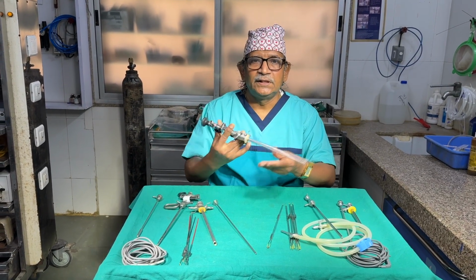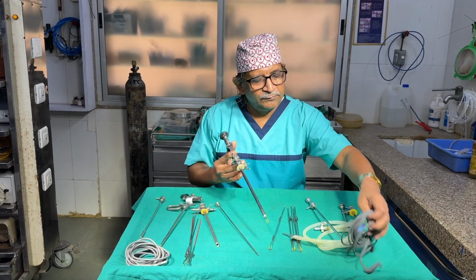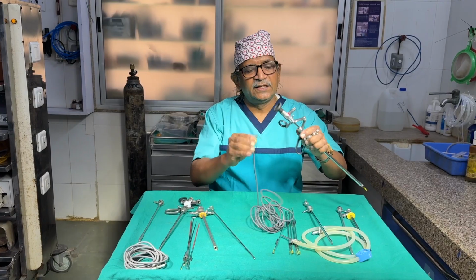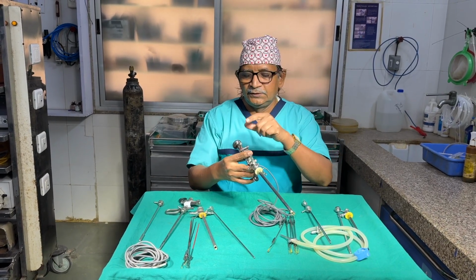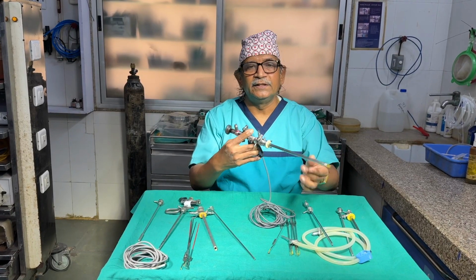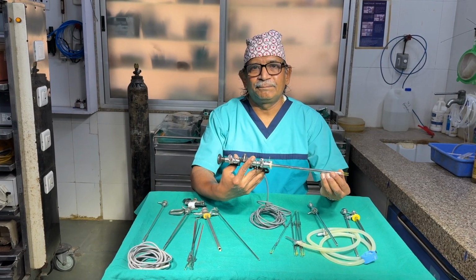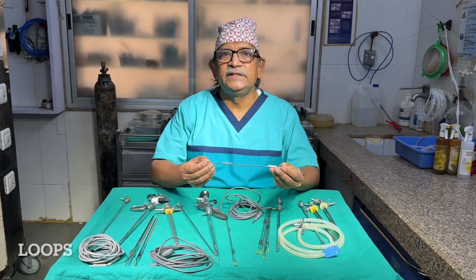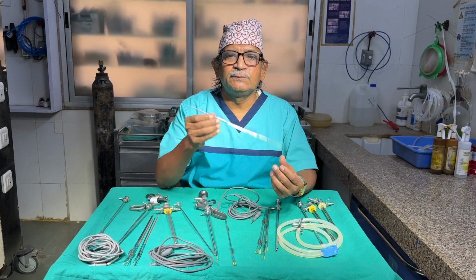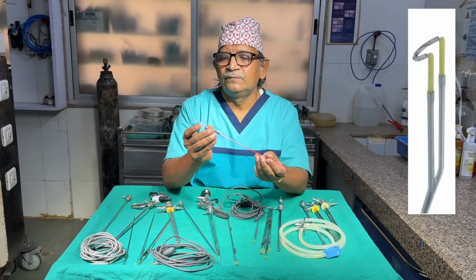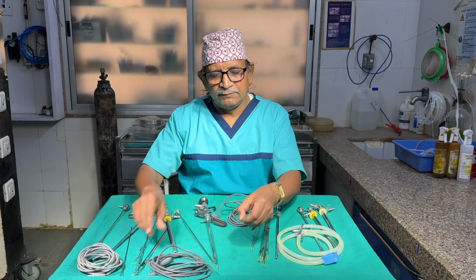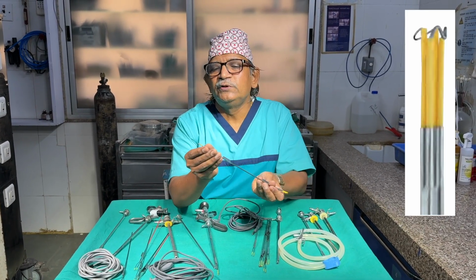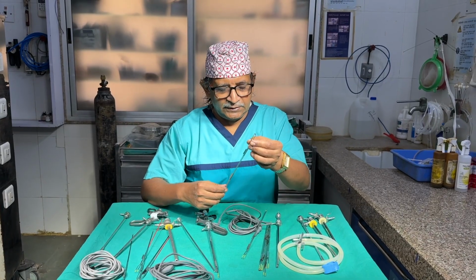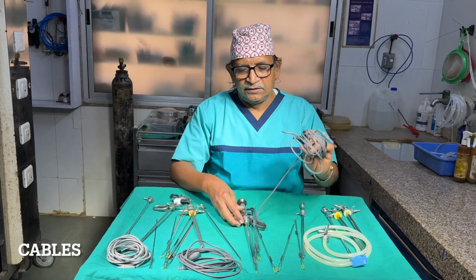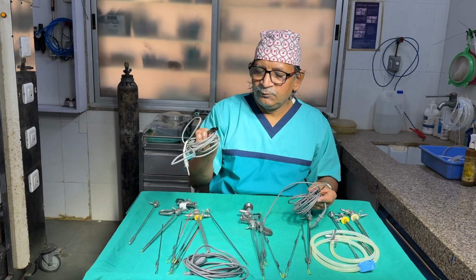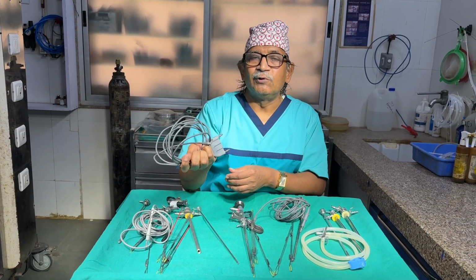So this is the assembled resectoscope, and we will be attaching our diathermy or cautery attachment to this resectoscope. Light cable here, inlet here, outlet here. Now this is the complete assembly for the TURP. The loops for TURP come in different forms. This is the double stem, only one active electrode. This is a monopolar. Single stem, monopolar, only one active electrode. Whereas this is the bipolar loop, where there are two active electrodes in this sheath. And different cables. This is for the double stem loop, this cable is for the single stem loop, and this is for the bipolar TURP.